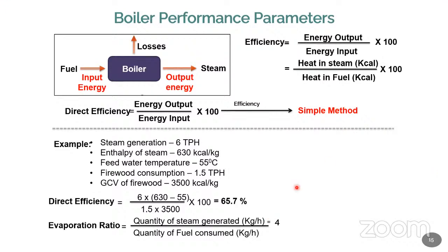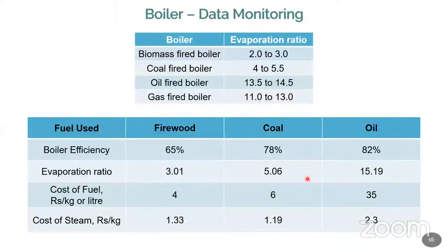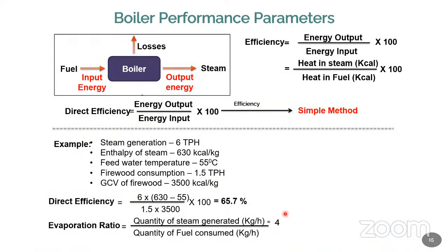Suppose the evaporation ratio is not good, what is the meaning of that? Suppose the desired value, if it's a coal-fired boiler, is 4.4 to 5.5. Say, for example, it's going to be 3 for a coal-fired boiler. What is the meaning of that? If it is 3, it means you are consuming more fuel. Am I correct? Because this is a lesser value. For producing the same amount of steam, you are consuming more fuel.